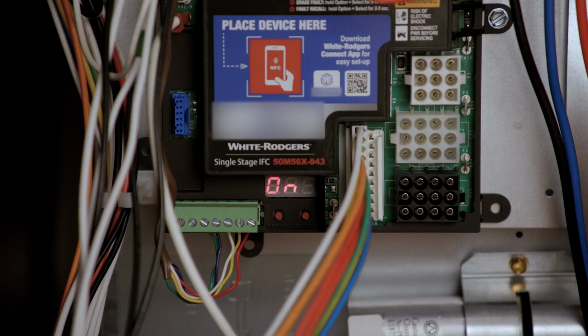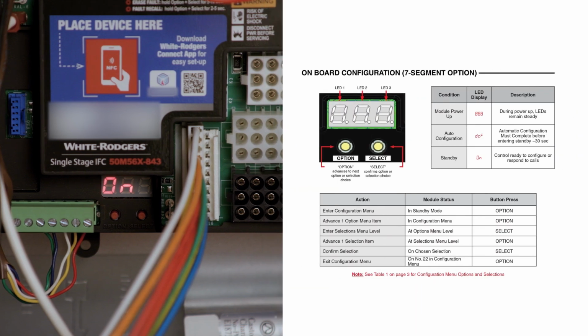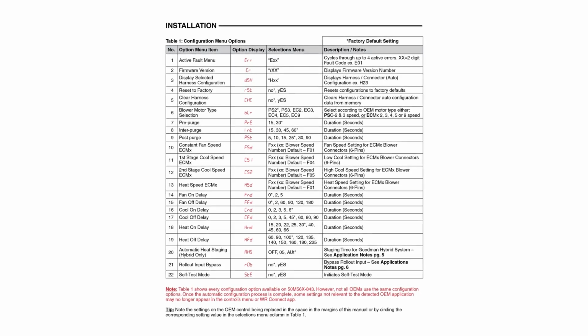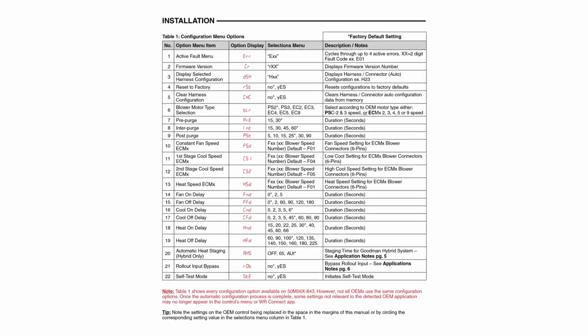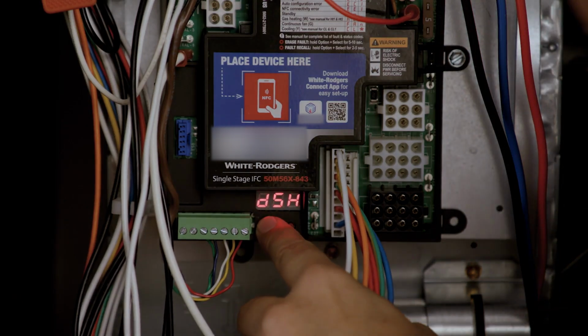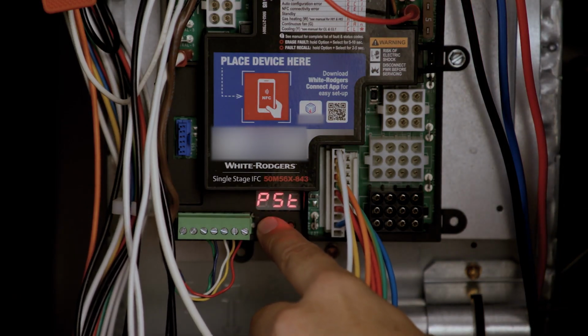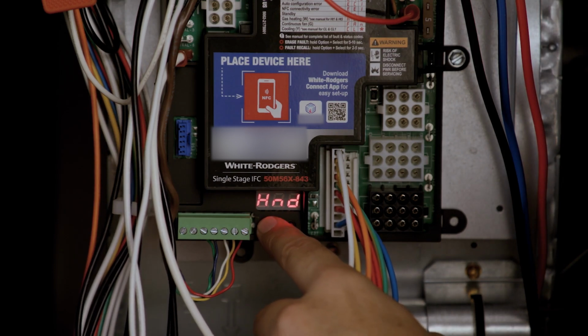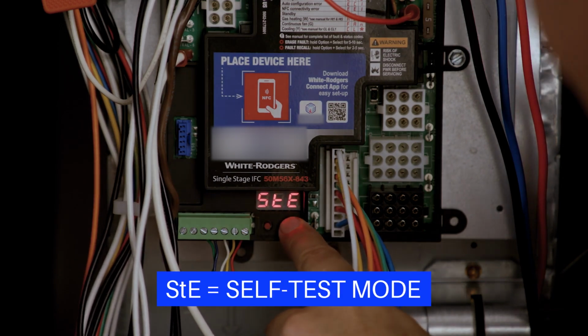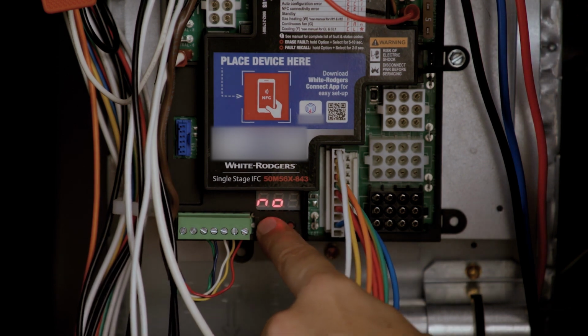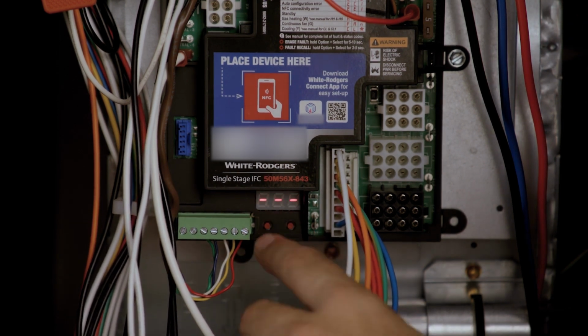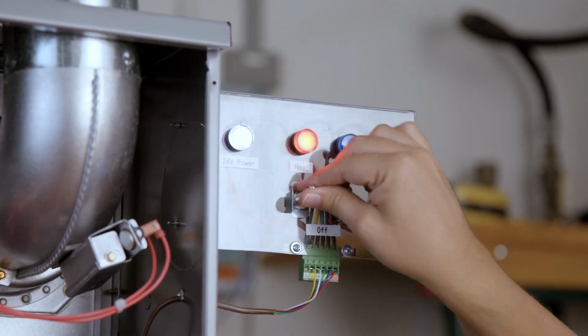If you chose not to configure timings with the White-Rodgers Connect app, the control can now be set up using the Option and Select buttons with the LED display. To enter configuration, press the Option button while the unit is in standby. Table 1 on page 3 of the installation instructions show configuration options. A self-test mode allows the control to test most furnace components without requiring a call for heat. To enter the self-test mode, go into the configuration settings and choose Yes on option number 22. To verify proper ignition, make a call for heat.